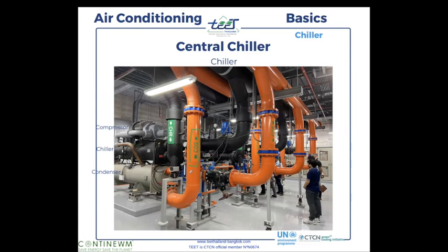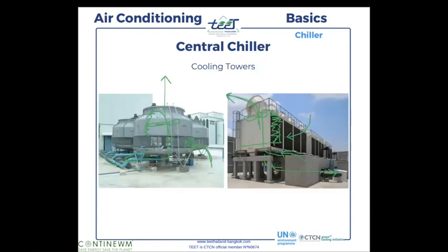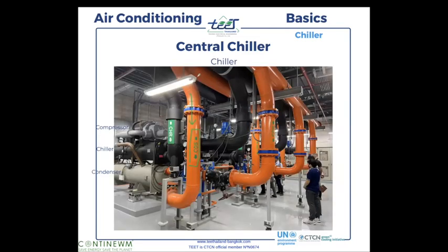So this water in this big yellow conduit is coming basically from the bottom of the tank here, from the cool water. It goes inside the building and comes in here. So this is basically the cold or warm water. It's not cold, but it's cooler than it was before, and it goes into the condenser.